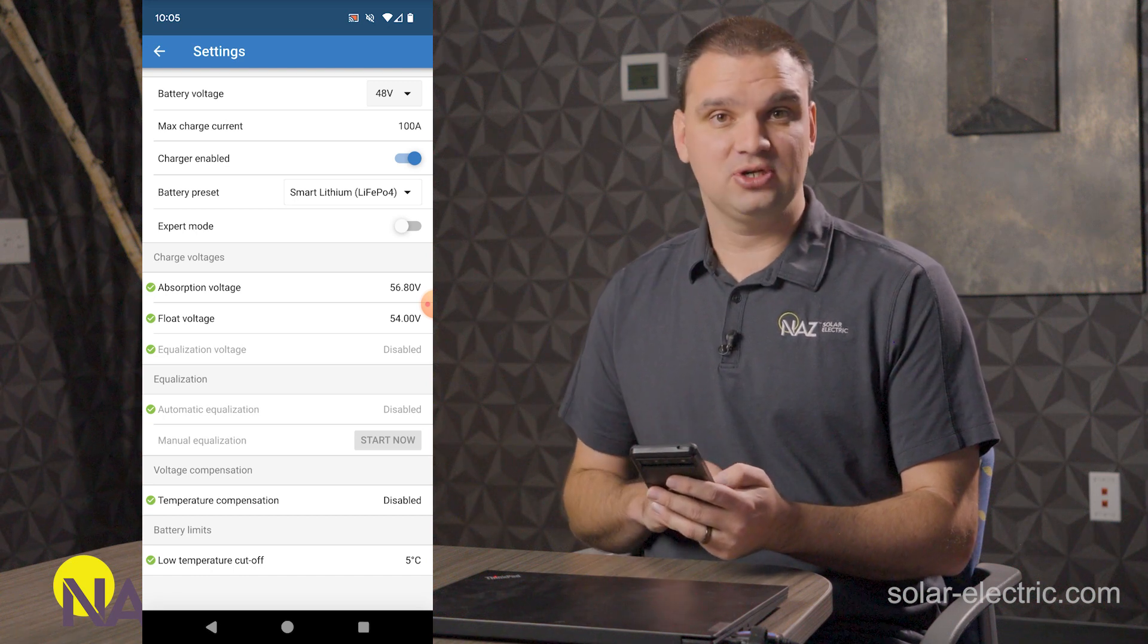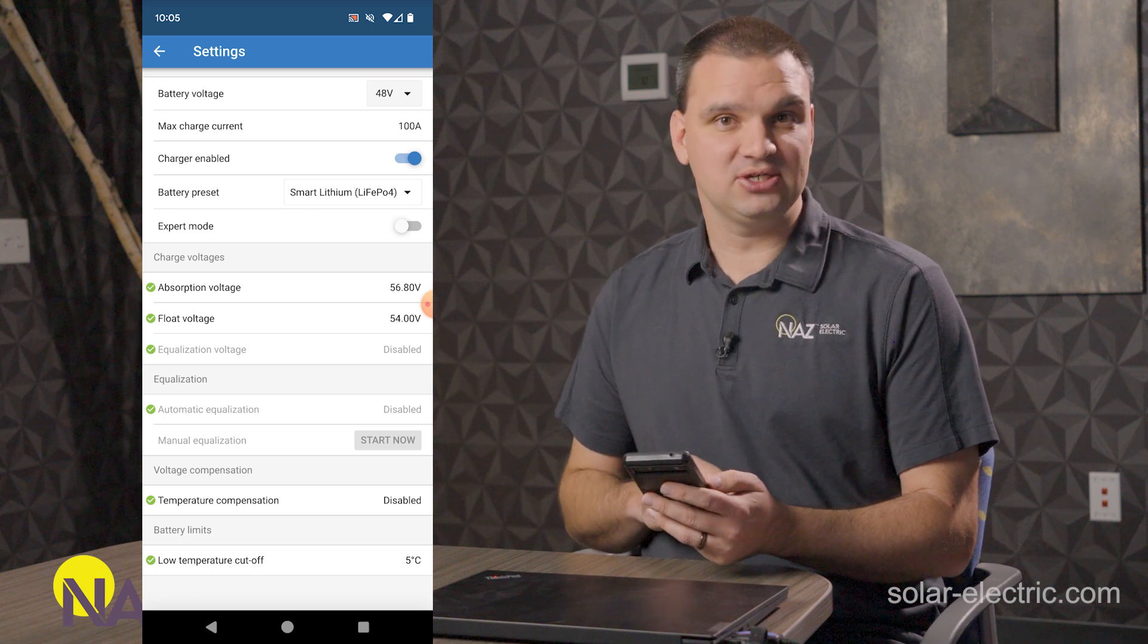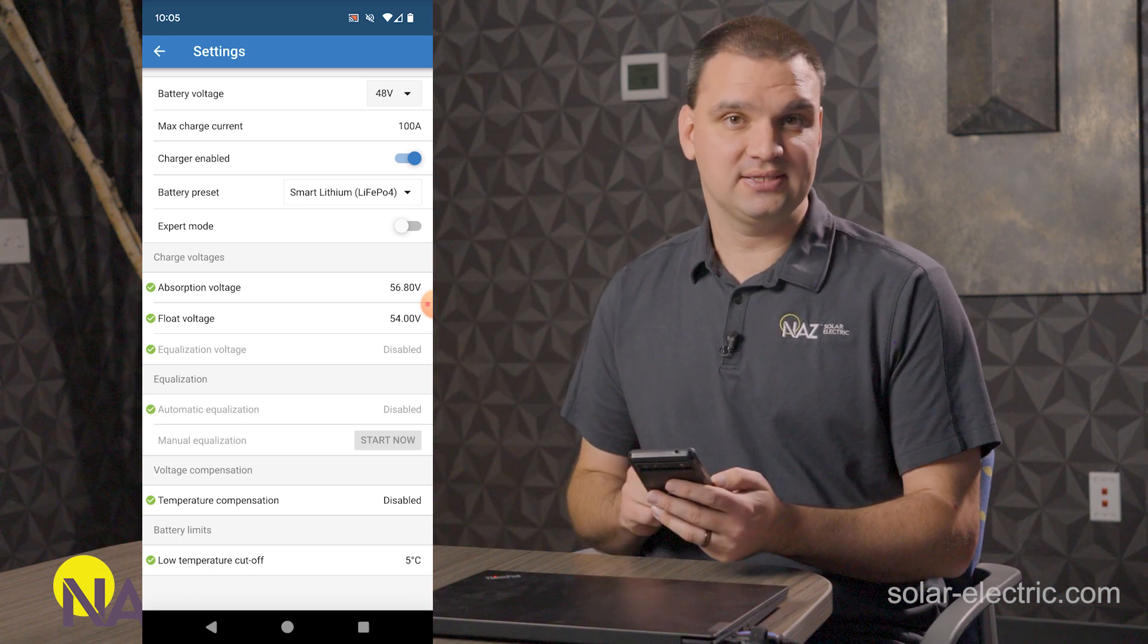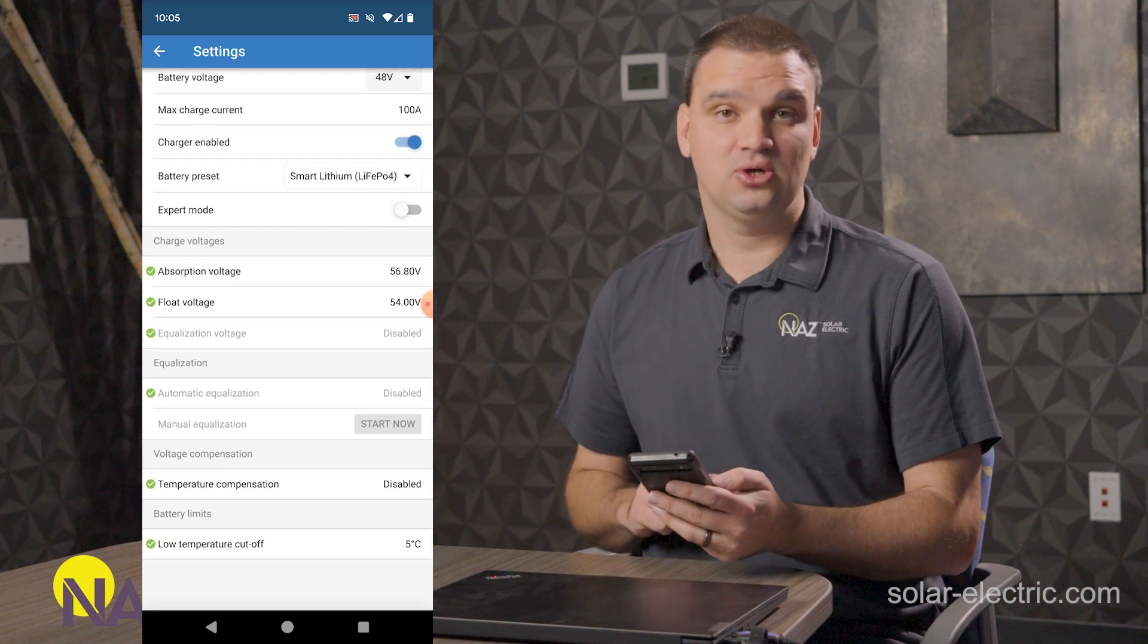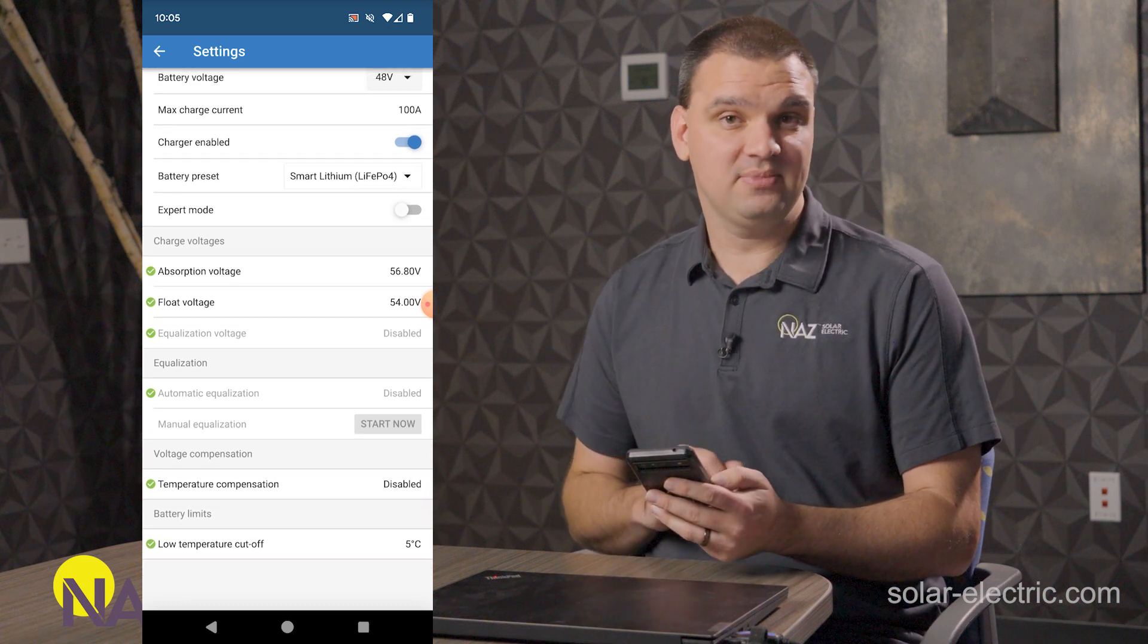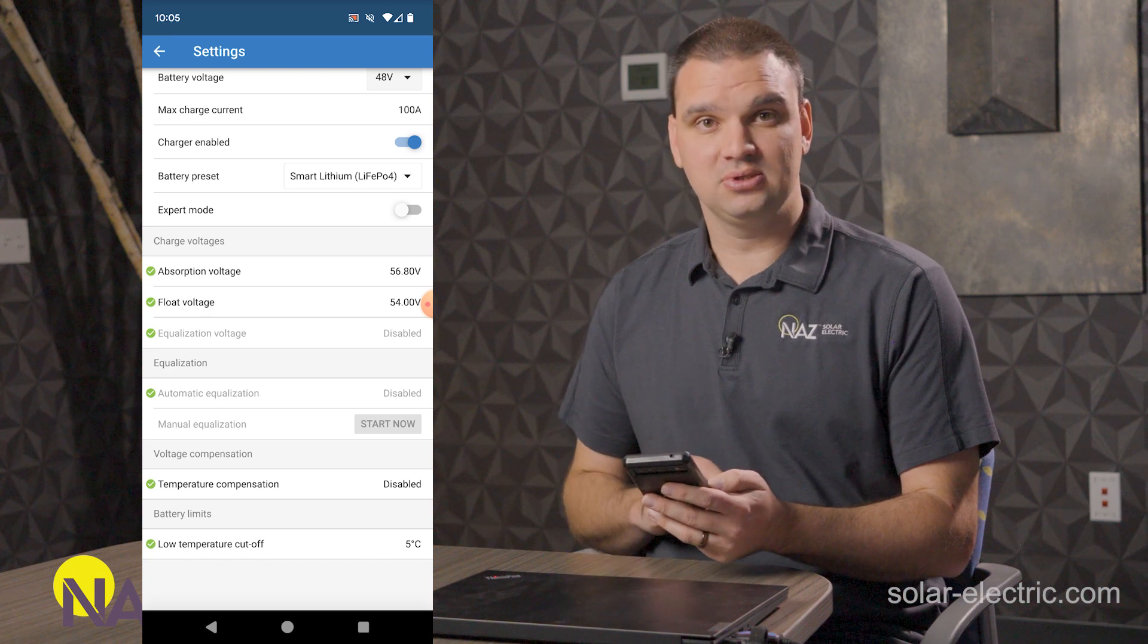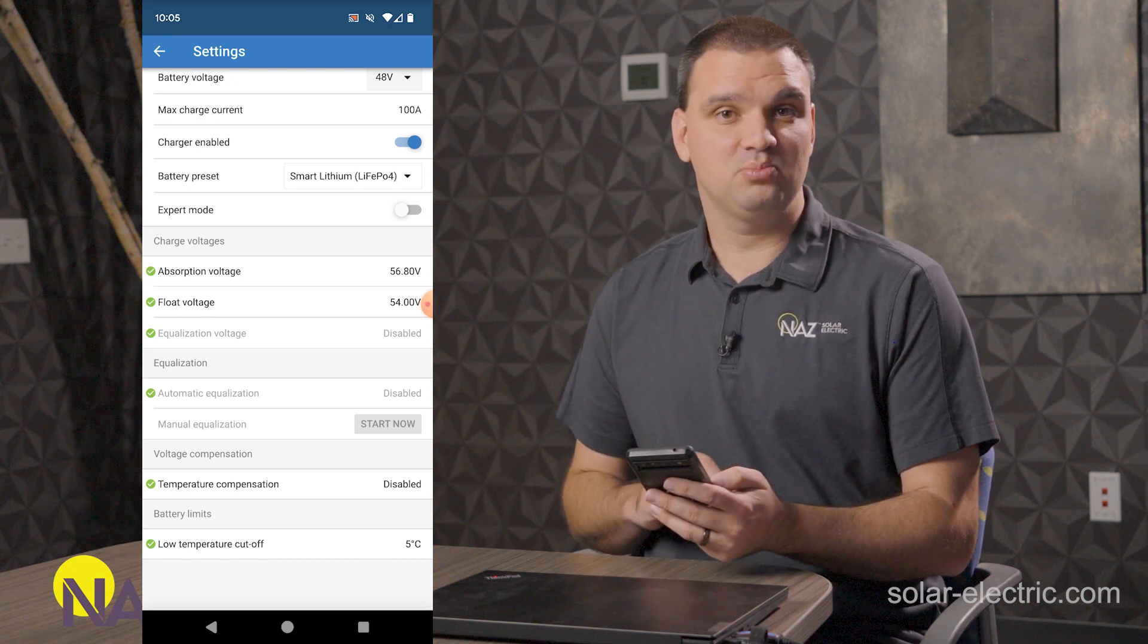You're going to want to make sure if you're using lithium batteries that you have equalization disabled because we don't equalize lithium batteries. We also don't temperature compensate charging lithium batteries. So you want to make sure that's disabled.